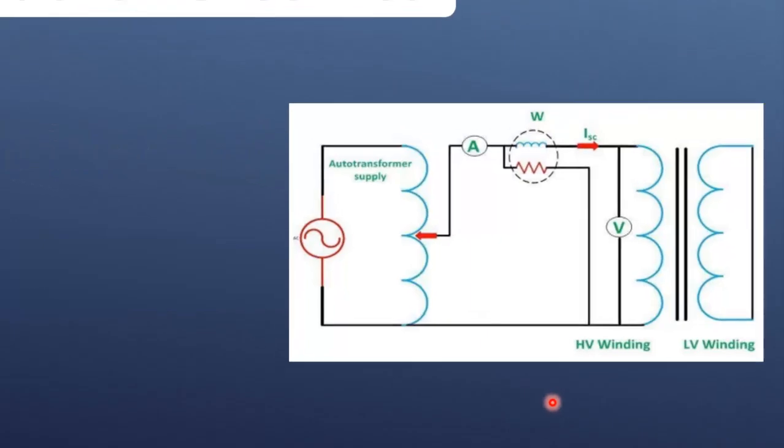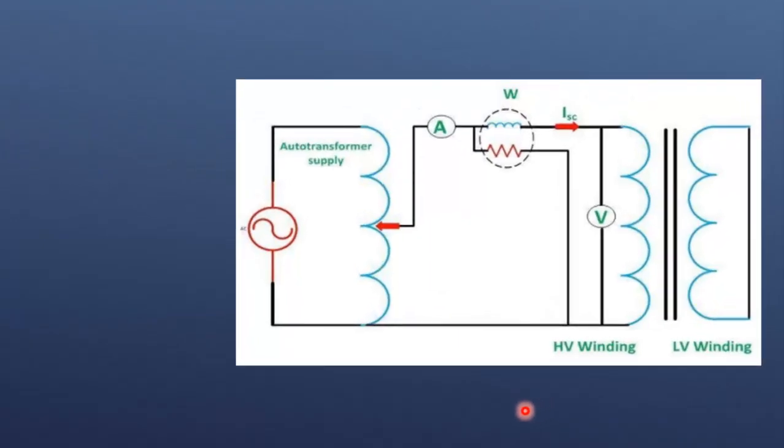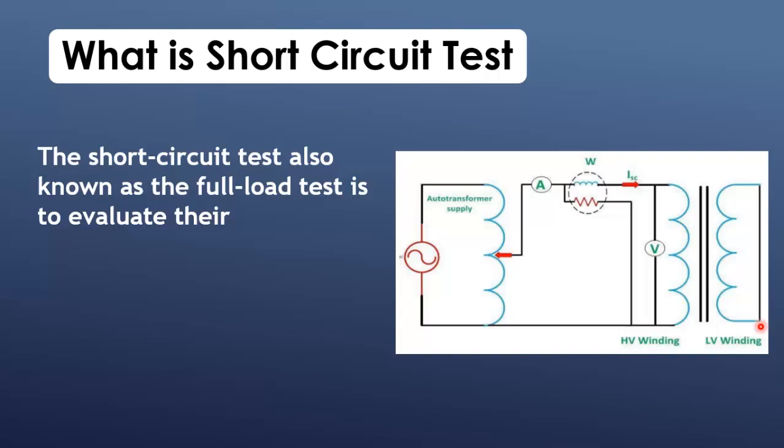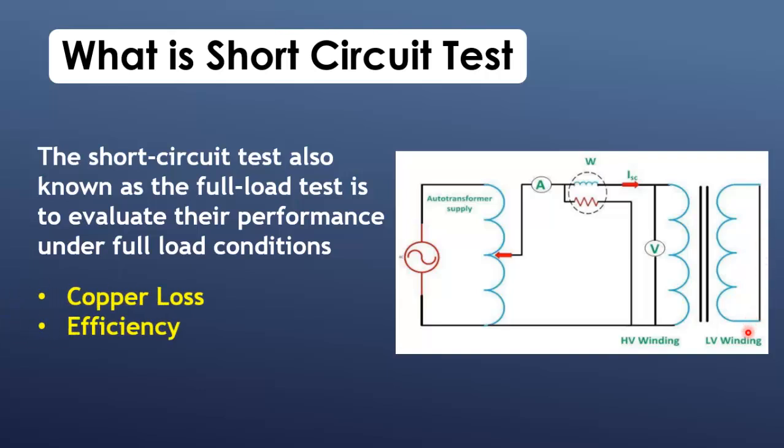Now we will learn what is short-circuit test of transformer. The short-circuit test, also known as the full-load test, is to evaluate transformer performance under full-load conditions. This includes copper loss, transformer efficiency, voltage regulation from no-load to full-load, and short-circuit impedance for short-circuit calculations.